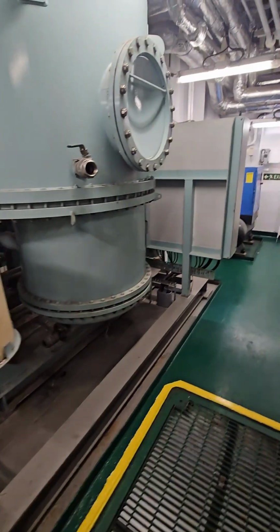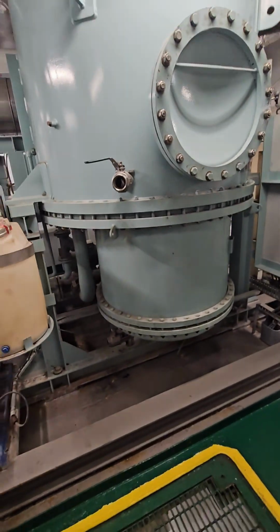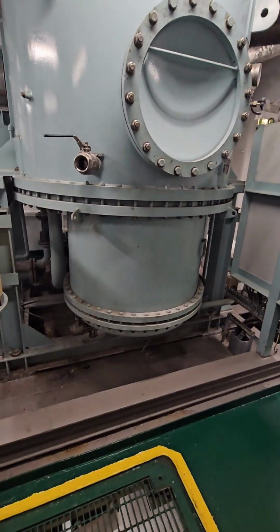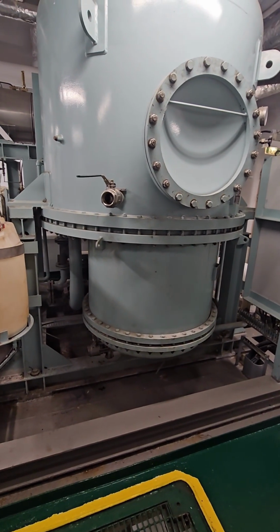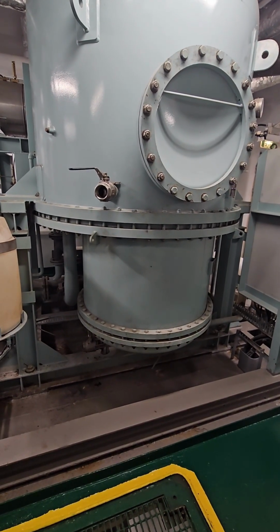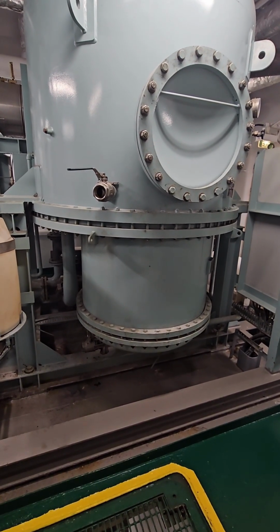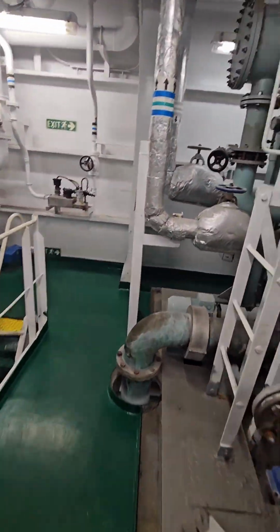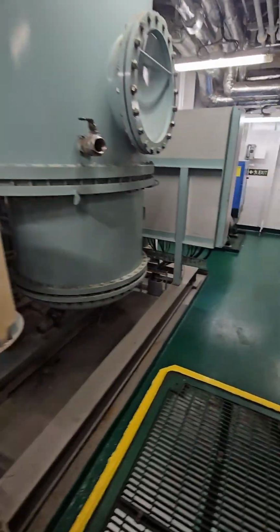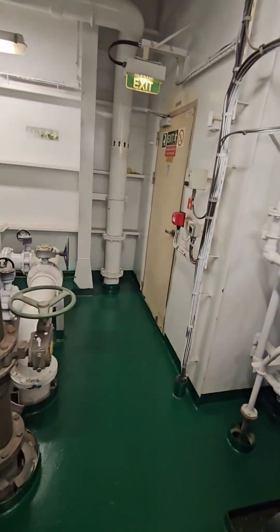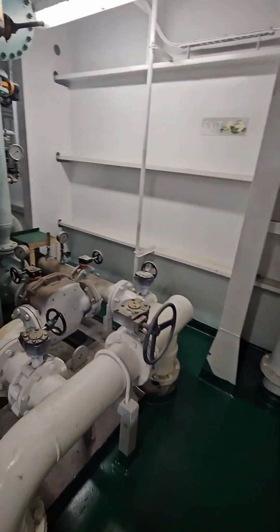Let's explain the evaporator's role in detail. Seawater enters the evaporator chamber as feed water. Hot water from the main engine's high-temperature HT jacket cooling system flows through tubes or plates inside the evaporator. This transfers heat to the seawater. Because the entire chamber is under vacuum, the boiling point drops significantly, to around 40 to 65 degrees Celsius instead of 100 degrees Celsius. The seawater evaporates into vapor.